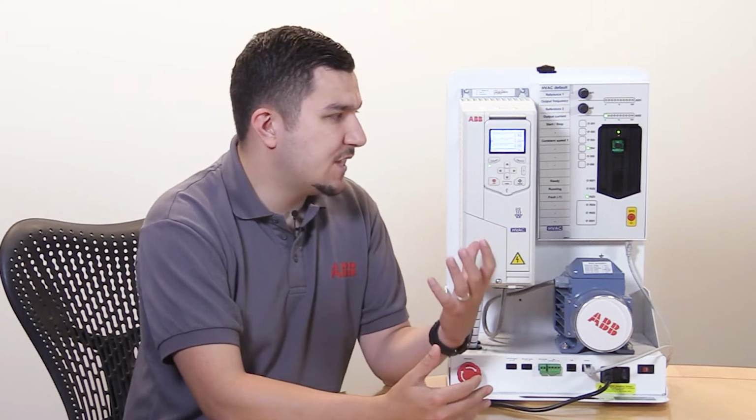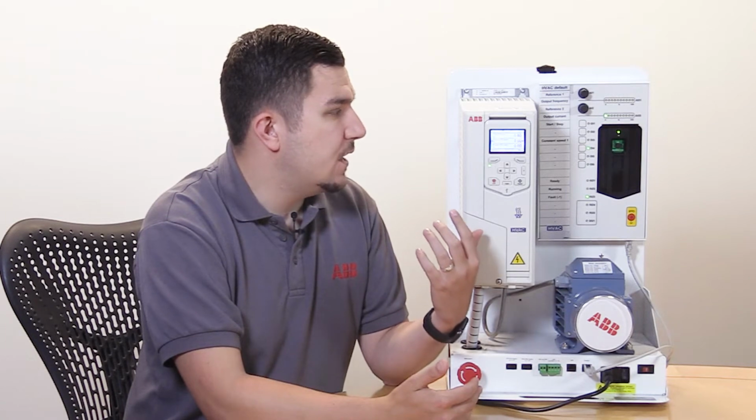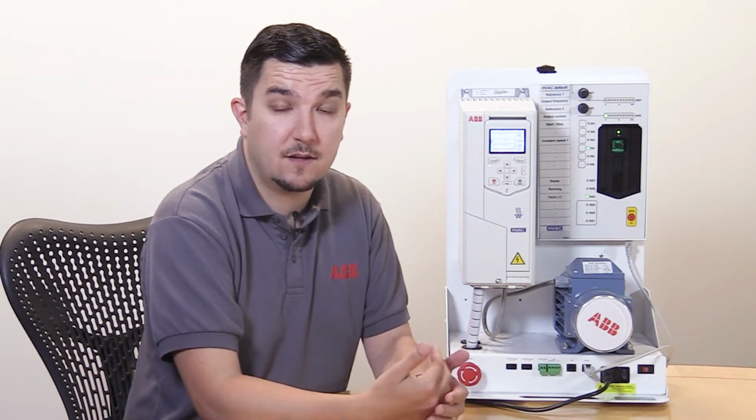So in this example that we're going to run through using the primary settings, with the ACH580, we're going to set it up so that we've got a hot water pump system, where the water in the system is very cold. We're going to give it a set point, so then what will happen is that we speed up to heat that water up in the system, and then when we get to that set point, you're going to see the drive and the motor slow down, to back off basically to a point where it could come to a standstill, or it just may creep very slowly depending on the behaviour of the system.